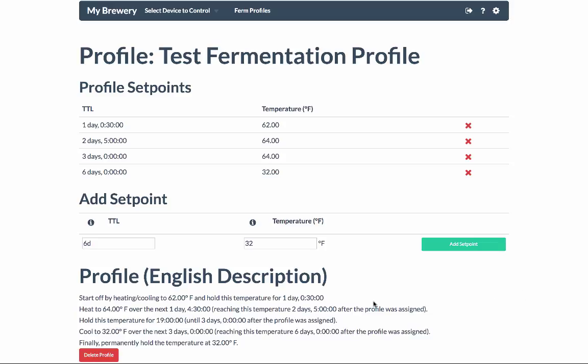There is a description of what these set points do down below, but what effectively happens is that it starts out and it will just hold the temperature using the first set point. So it will hold 62 degrees Fahrenheit for 1 day and 30 minutes. After that, it will heat to 64 degrees Fahrenheit until 2 days have passed since the start of the profile.